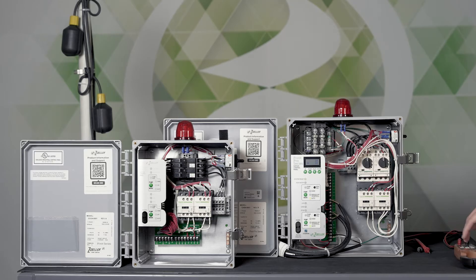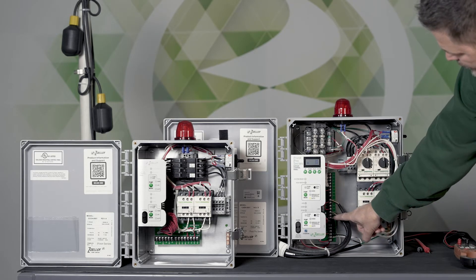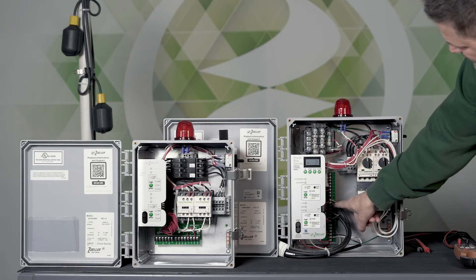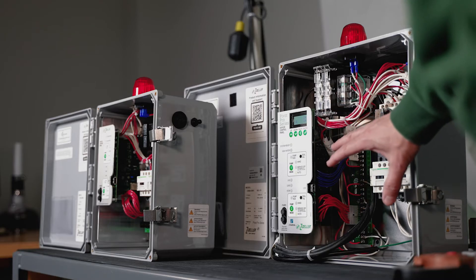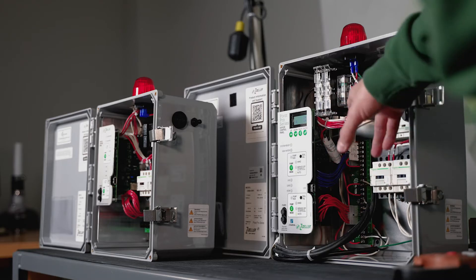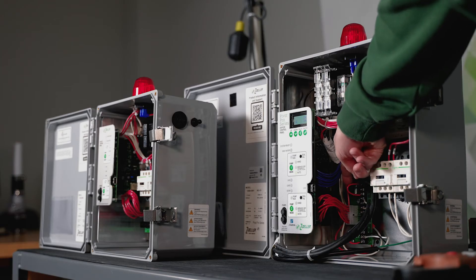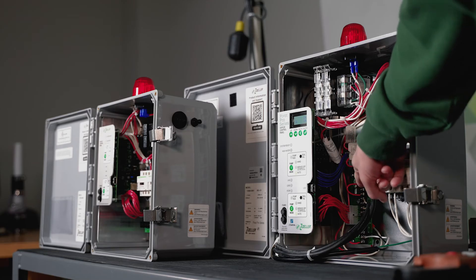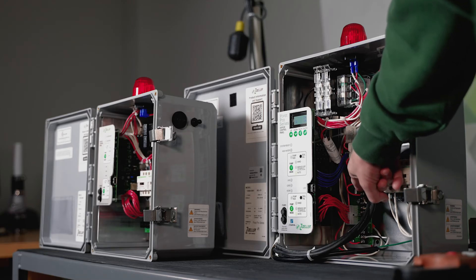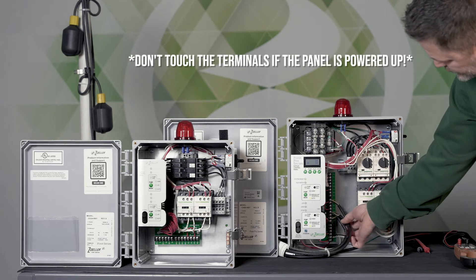Let's talk about how the float switches connect. You've got four positions on the terminal board: stop, lead, lag, and high. By default, any duplex panel shipped from the factory is going to have a red wire jumper that jumpers the lag float to the high float, so you really only need three float switches.